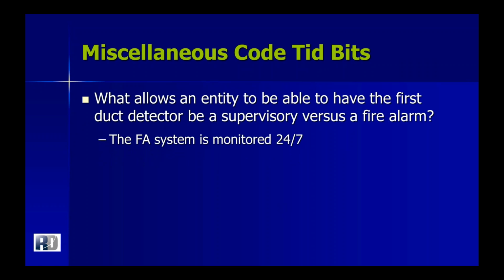The fire alarm systems, little delay there. When fire alarm systems are monitored 24/7, a person on site, the smoke duct detectors can be set up as a supervisory device. But if they're not monitored 24/7 with an entity on site, more or less at a fire alarm panel, then those devices would have to be a fire alarm, which would then roll the fire trucks. So it depends on the entity that you are building and how it's being monitored on whether or not a duct detector is supervisory or an alarm.